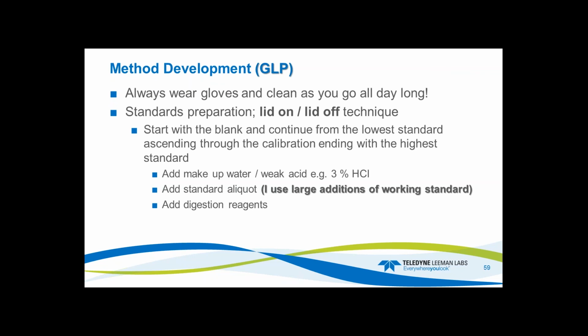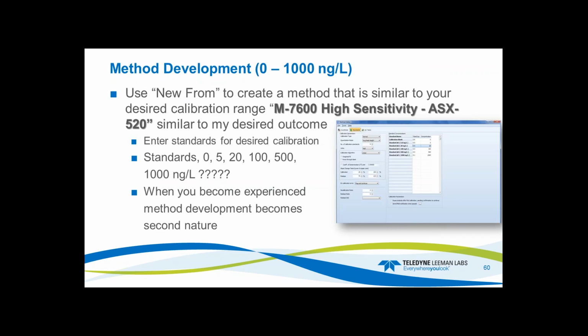And then finally you add your digestion reagents. It's very important to matrix match. So in this case, I'm going to look at developing a method from 0 to 1,000 nanograms per liter. I pulled a high sensitivity method right out of the template, and I entered my standards: 0, 5, 20, 100, 500, 1,000 nanograms per liter. Will that work? I don't know. I'm going to give it a go.